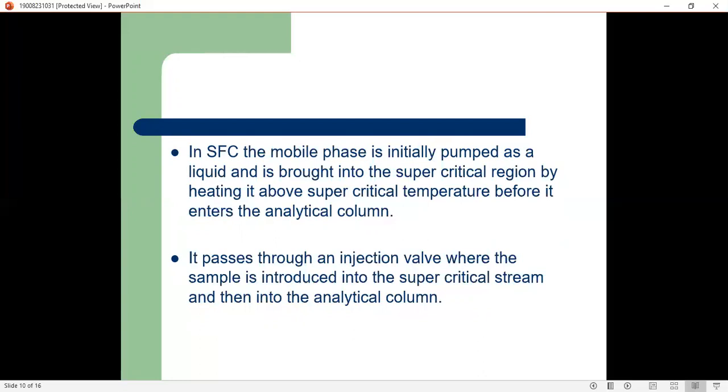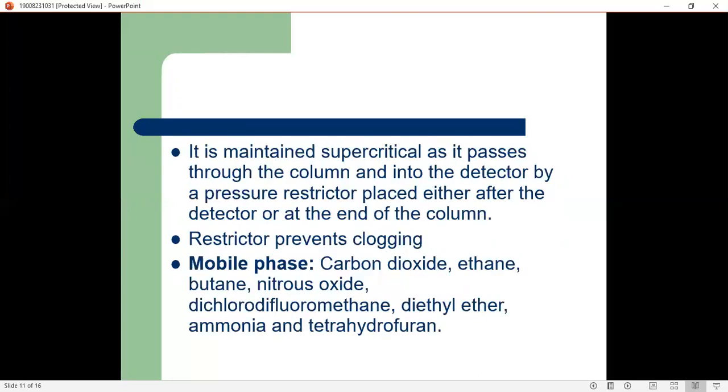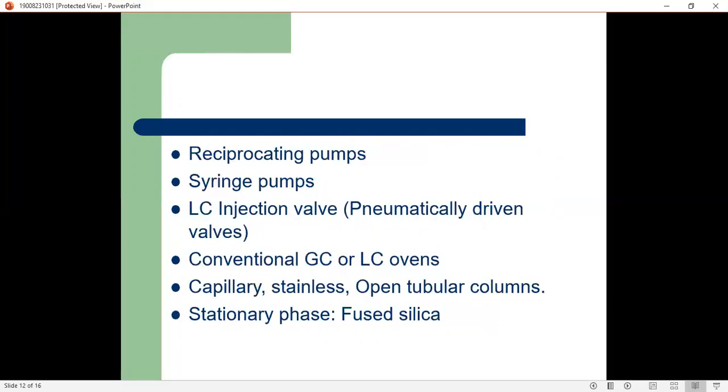The sample is introduced into the supercritical stream and then into the analytical column. It is maintained supercritical as it passes through the column and into the detector by a pressure restrictor placed either after the detector or at the end of the column. The restrictor prevents clogging. The mobile phase includes carbon dioxide, ethane, butane, nitrous oxide, dichlorodifluoromethane, diethyl ether, ammonia, and tetrahydrofuran.